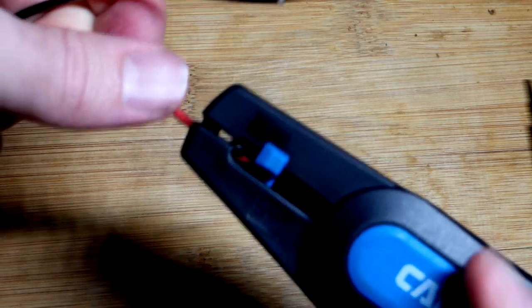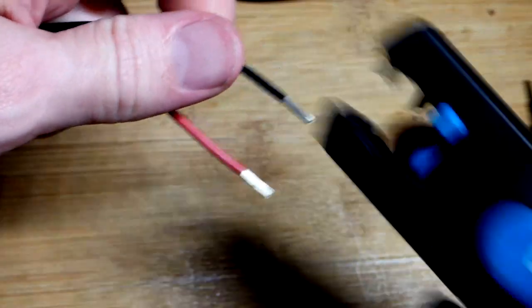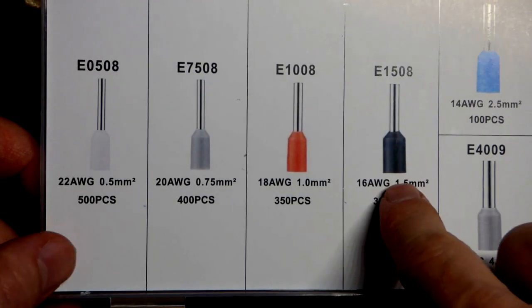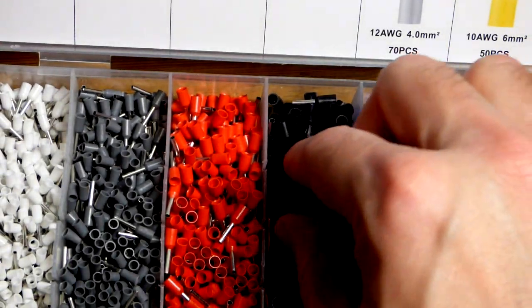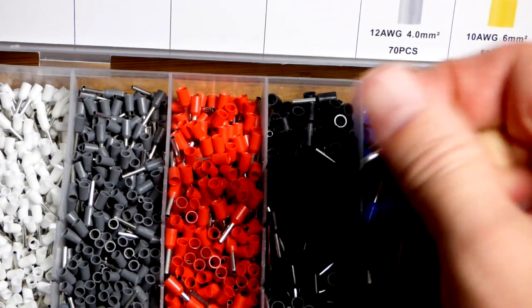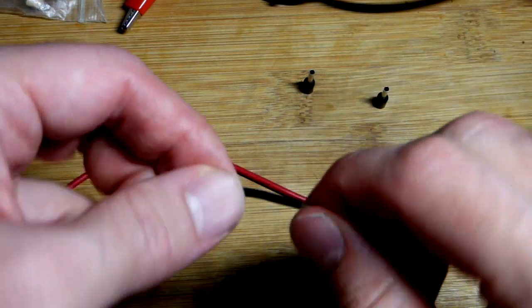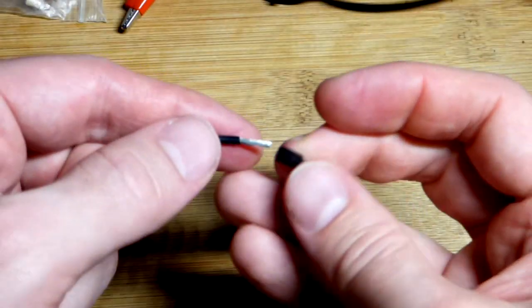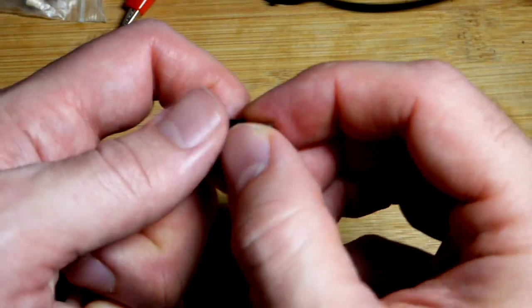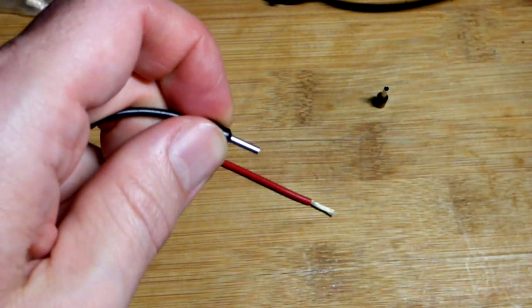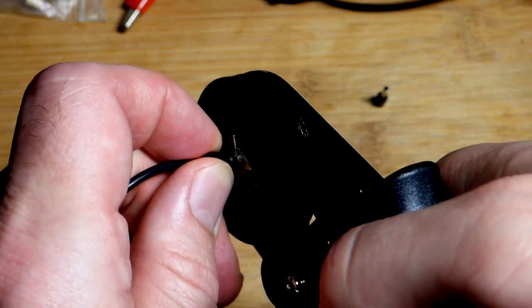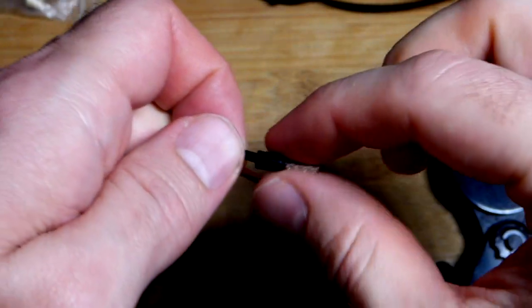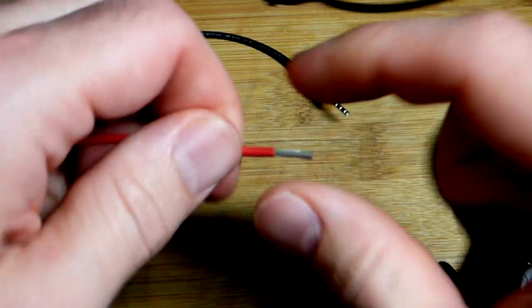So now I unplugged them, you got to pull pretty hard to unplug them, but they came unplugged at some point. Going to strip the end of the wires again now that they aren't connected to anything. So now we're going to crimp a ferrule to it. This is before it is crimped. 16 American Wire Gauge is the black one. You can see how many you get with this particular kit. I plan to put links for everything down at the bottom that I'm using in this video. So there we go, we got two of them. This is a real easy crimping. Again, we're just twisting the wire, just giving it a little bit of a spin so they stick together a little more. Push that all the way, with the tongue the shortest distance it's not sticking out at all. That was the tongue of the wire stripper I meant. We just put it in, make sure it only closes on the metal, not on the plastic. Just squeeze her down and there we got a crimp, really solid.